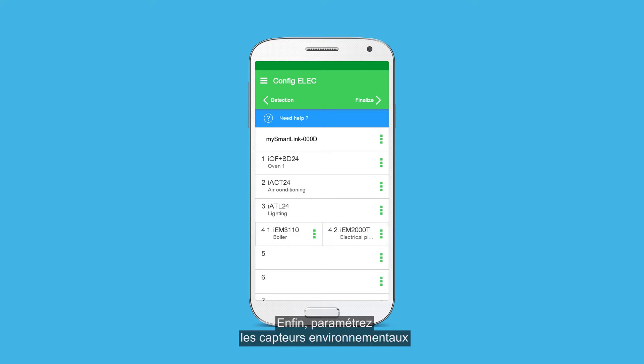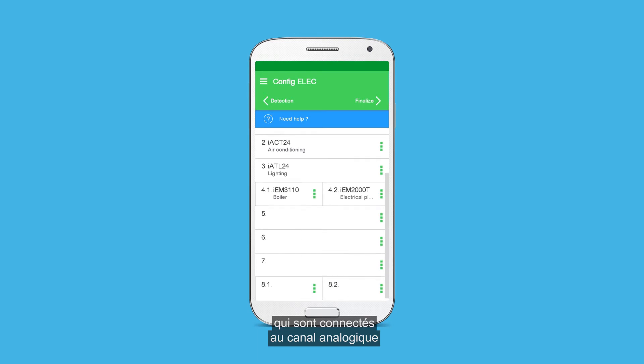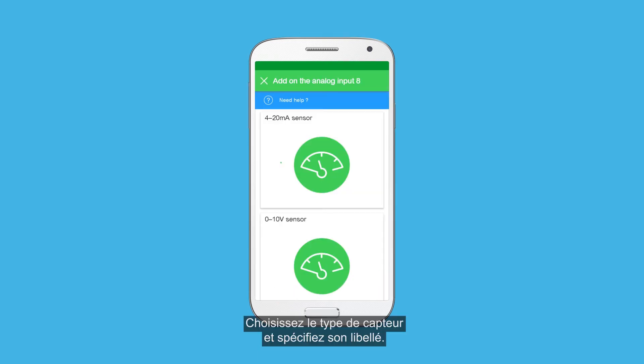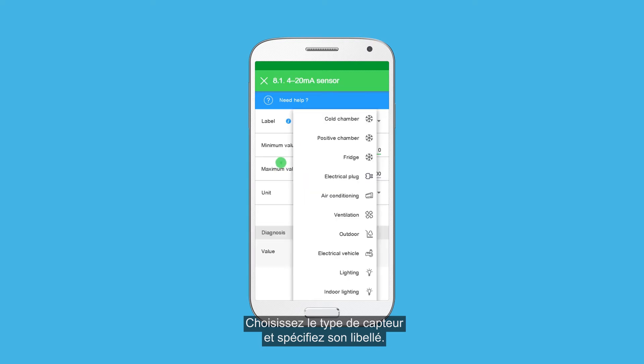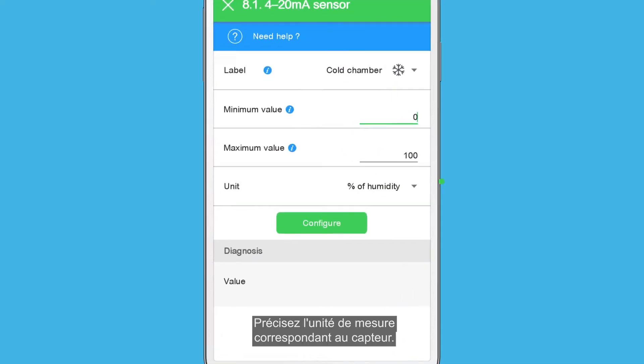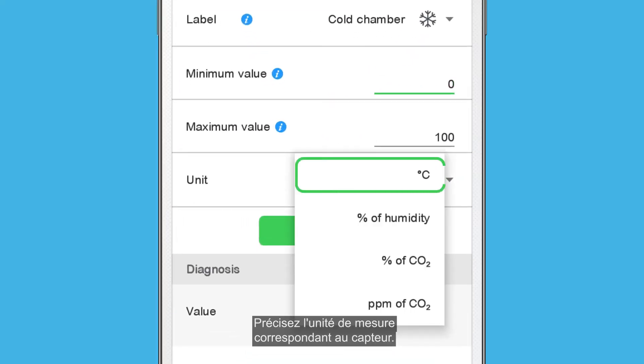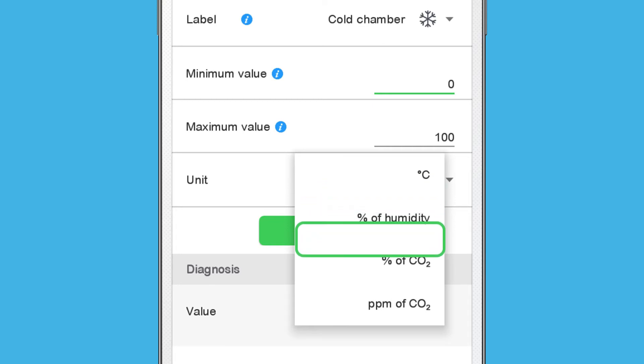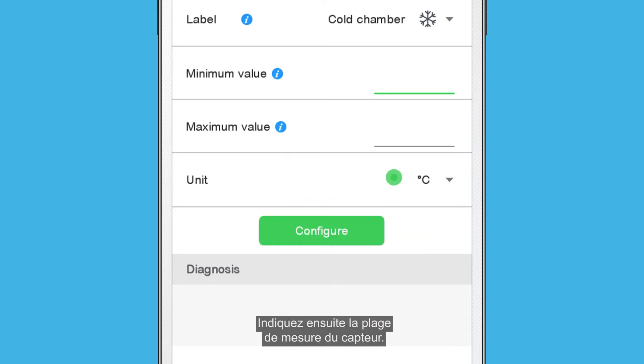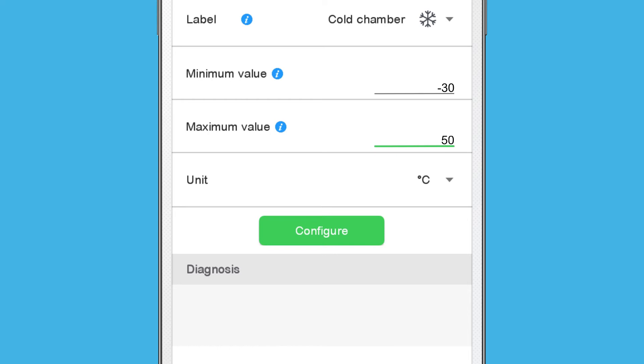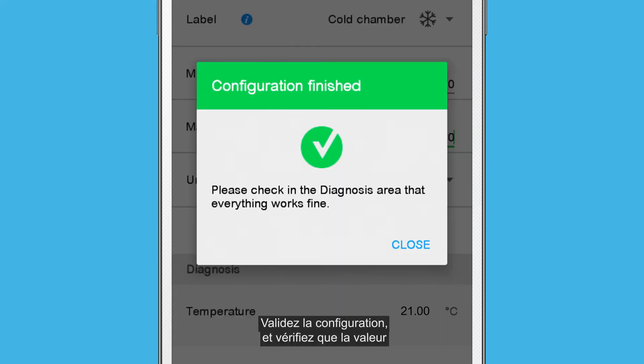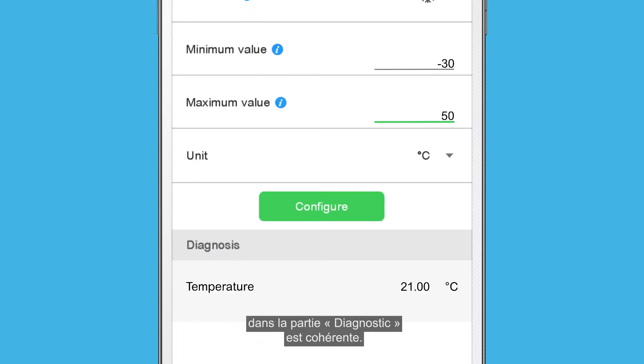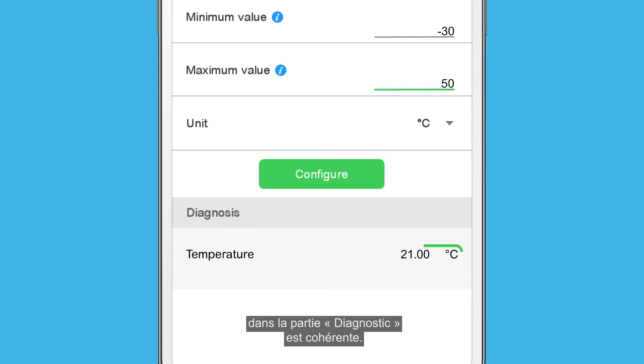Finally, configure the environmental sensors that are connected to the analog input numbers 8.1 or 8.2. Choose the type of sensor and specify its label. Specify the measurement unit of the sensor, then specify the measurement range of the sensor. Validate the configuration and verify that the value in the diagnosis section is correct.